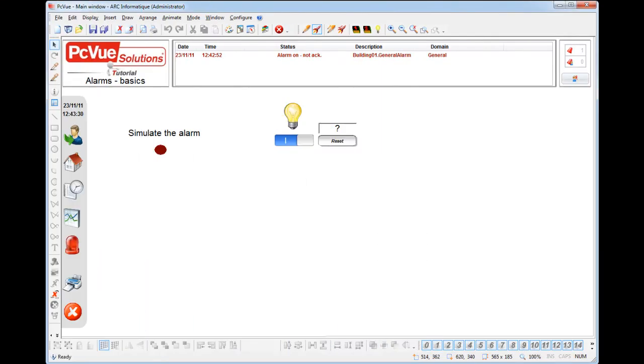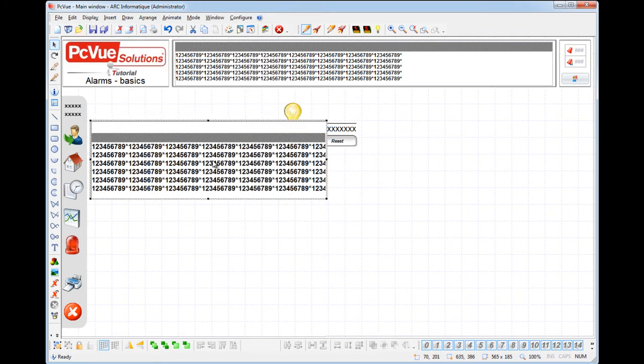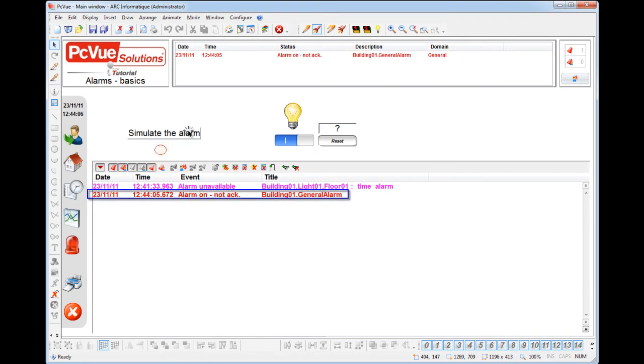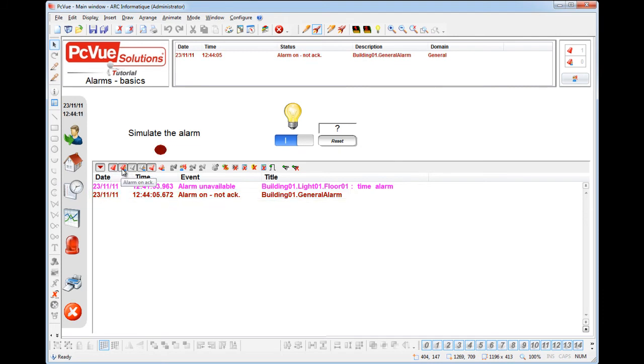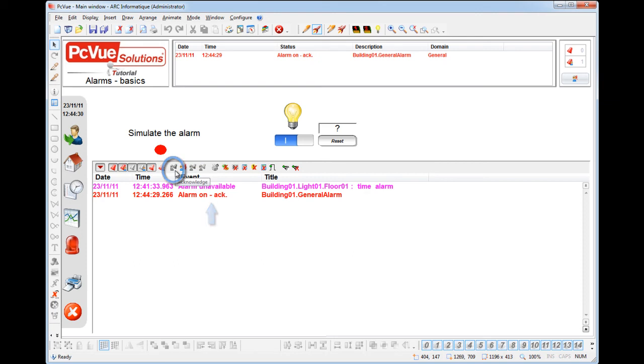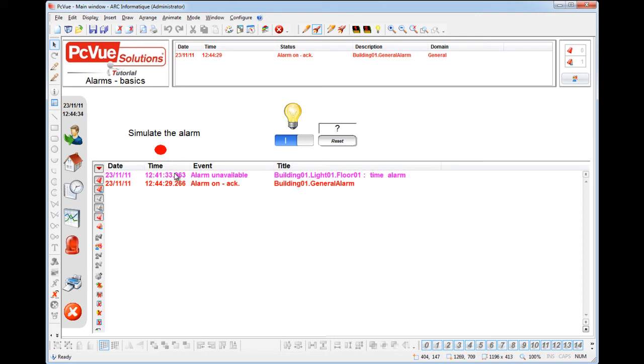The alarm viewer is a tool used to display a list of alarms and to allow the user to interact with the alarms by either acknowledging or masking them. You can insert an alarm viewer from the insert menu, and it's possible to insert different alarm viewers in the same screen and in the same project. Before going through its properties, let's see how the alarm viewer works in runtime. You can resize and move the alarm viewer anywhere in your mimic, as with any other object within PcVue. When you simulate an alarm, you can see its status in the viewer. The menu allows filtering the list by different statuses — for example, filtering alarm unavailable. You can also acknowledge, mask, and unmask alarms. To acknowledge an alarm, just select it from the list and click on the button from the menu. The alarm has been acknowledged. If you right-click on the menu, you can change the location of the menu and even its content.